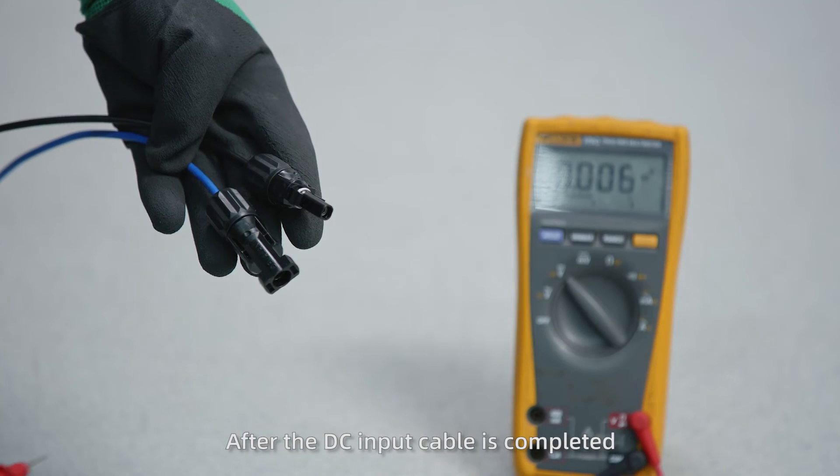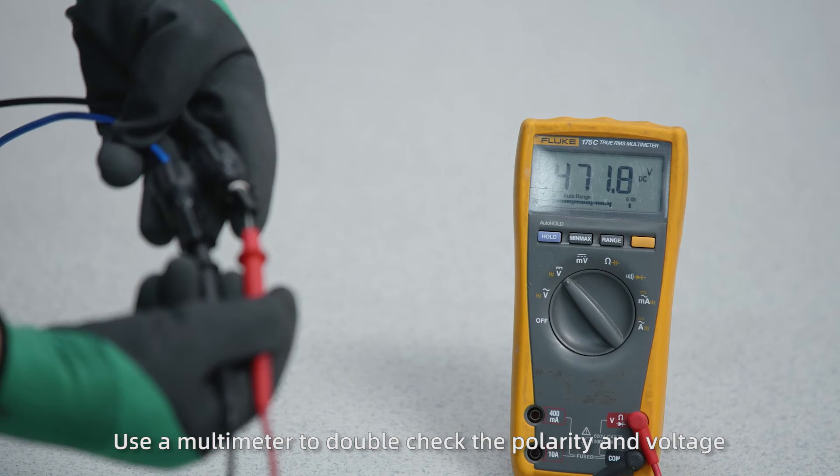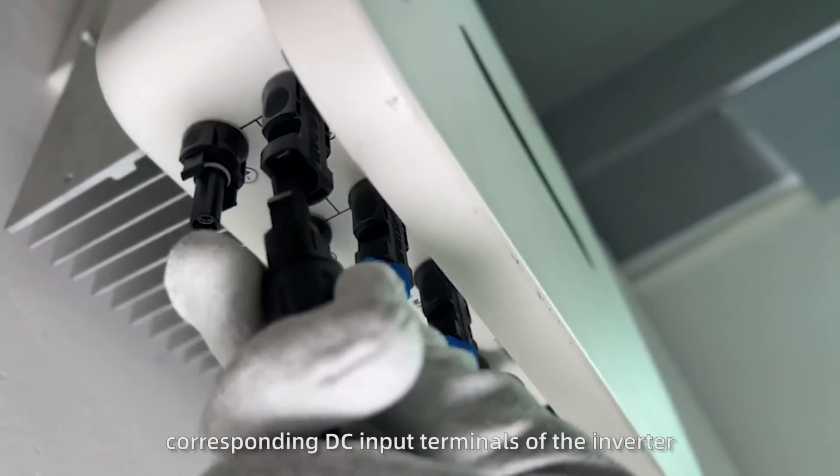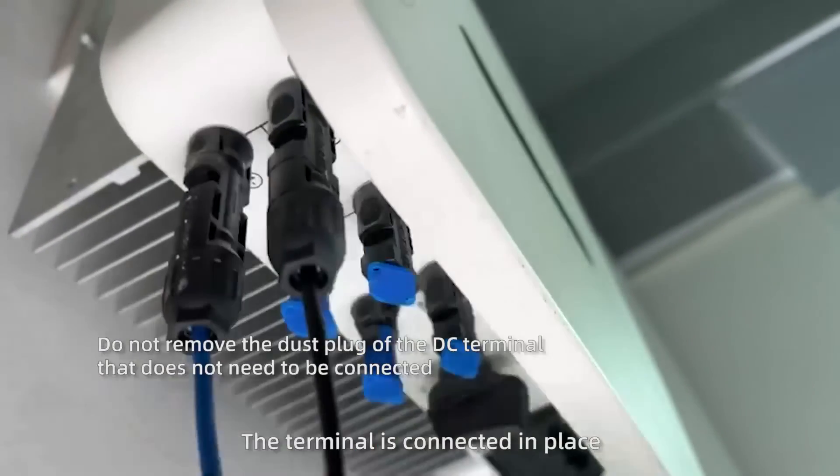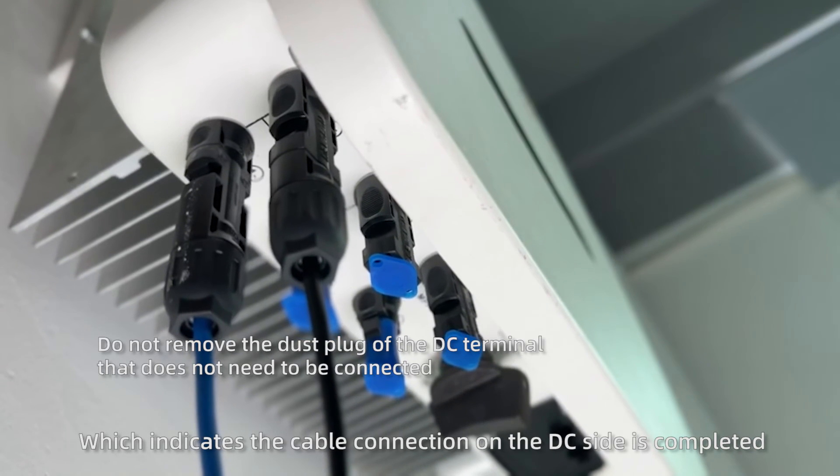After the DC input cable is completed, use a multimeter to double check the polarity and voltage. Then insert the positive and negative connectors into the corresponding DC input terminals of the inverter. When you hear a click sound, the terminal is connected in place, which indicates the cable connection on the DC side is completed.